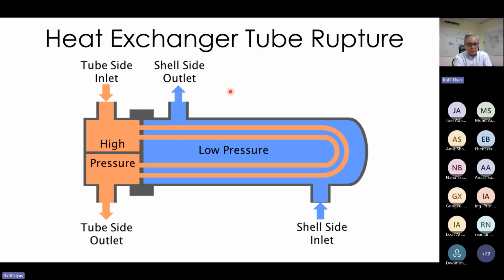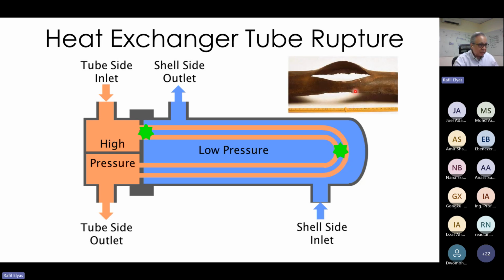Okay, so what do we mean by heat exchanger tube rupture? If we take a look at the schematic of a shell and tube heat exchanger, in this case we've got high pressure gas in the tubes and lower pressure on the shell side. You can typically expect potential failure at the tube sheet over here and potentially at the tube bend. That's an example of a ruptured tube. Now, in our case, we typically assume a simple guillotine rupture, nothing as complex as that, with gas coming from two different sides of the tube.